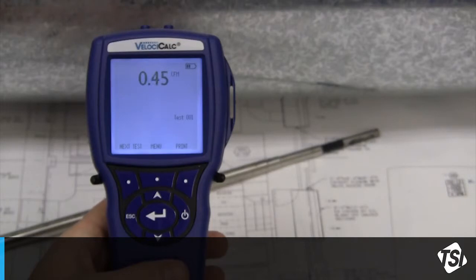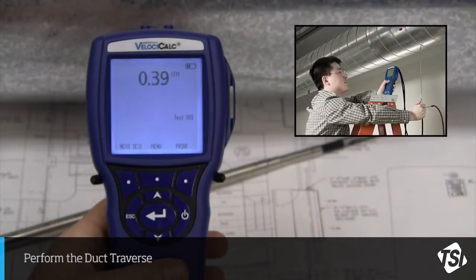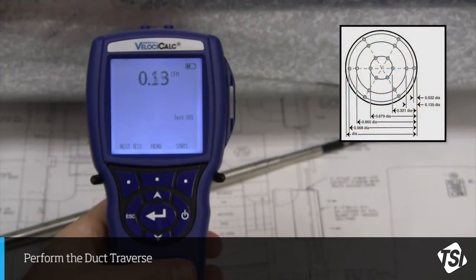Press Enter when the probe is in the proper position within the duct. The unit will display a cylinder with an arrow pointing to it, and it will count down from your selected sample time. In this case, it will count down from 10, according to the sample time I selected earlier. I would do this same step, pressing the Enter button and waiting for the 10-second countdown at each of the points in my duct traverse.